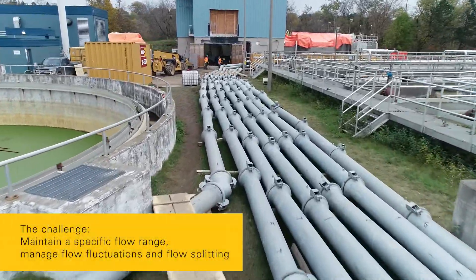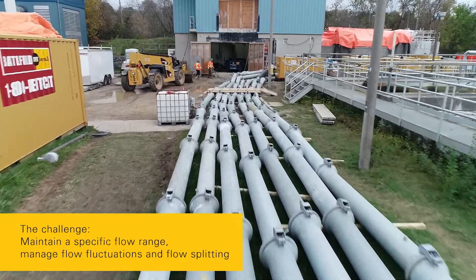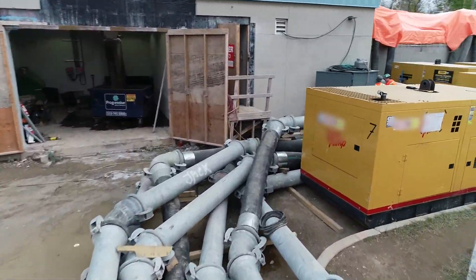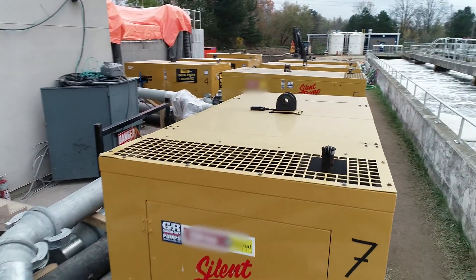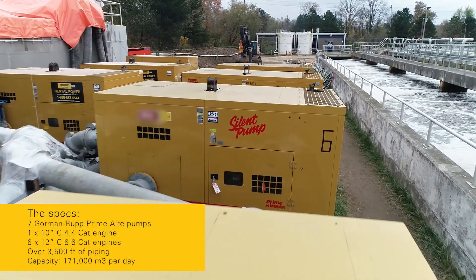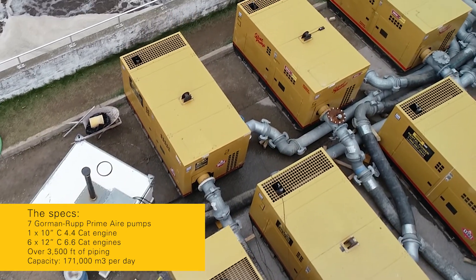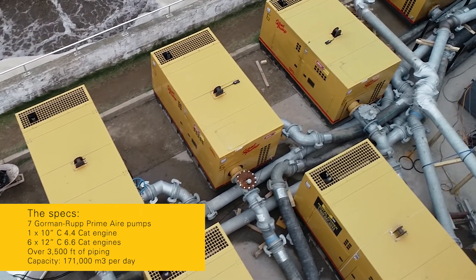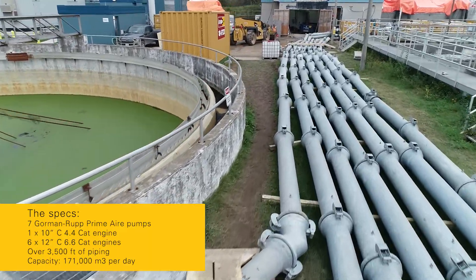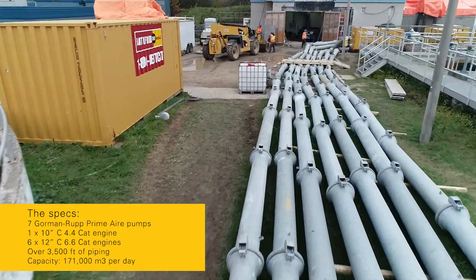The system was engineered to handle a specific peak and average flow range, as well as manage flow fluctuations, all while splitting flows at desired ratios. This critical installation uses seven Gorman-Rupp pumps with high-performance CAT engines and over 3,500 feet of piping to pump up to 171,000 cubic meters of wastewater per day.